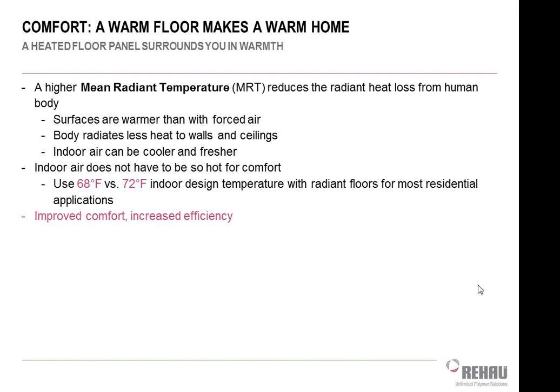But when I have a radiant system, the difference is that if I keep all the surfaces warmer than my human body, then those surfaces are now shining their energy to me. So if my floor is no longer a cool 65 degrees, and instead that floor is a warm 95 degrees, and my skin is 91 or 92, that floor is transferring energy to me instead of me getting my energy sucked away. That's the premise of a radiant system: the radiant floor or the radiator panel or the ceiling or whatever it's going to be is shining energy to me in the wintertime because it is slightly warmer than my skin temperature.